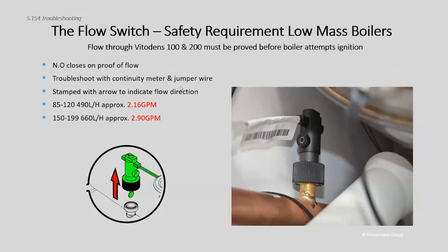We're going to show you how to troubleshoot the flow switch — very simple with a continuity meter. Something that measures open circuit and closed circuit. In troubleshooting, sometimes you might need a jumper wire to test the flow switch. If you're ever replacing the flow switch, it's worth pondering why it's being replaced. When you tap it back in, those flow switches are flow-sensitive — make sure the paddle is perpendicular in that copper pipe so it gets full-on flow as the pump runs. A lot of times when guys replace flow switches, if the paddle isn't in the right spot it might not get enough flow to push the paddle to the reliably closed position.